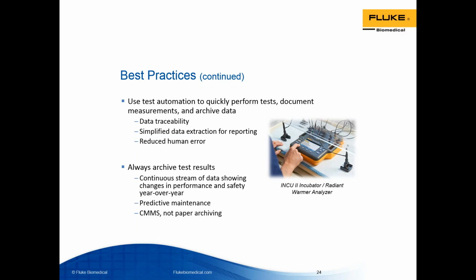We should always archive our test results. The purpose of testing and producing test results in the first place is to have a continuous stream of data showing all changes in the safety and performance of the incubator year over year. So long-term trending of this statistically relevant information provides the basis for predictive maintenance, like when the next repair is most likely to happen. So the parts, especially those long lead time and costly parts, can be ordered and received just in time for the repair event. This saves money and increases the amount of time the medical device is available for use.